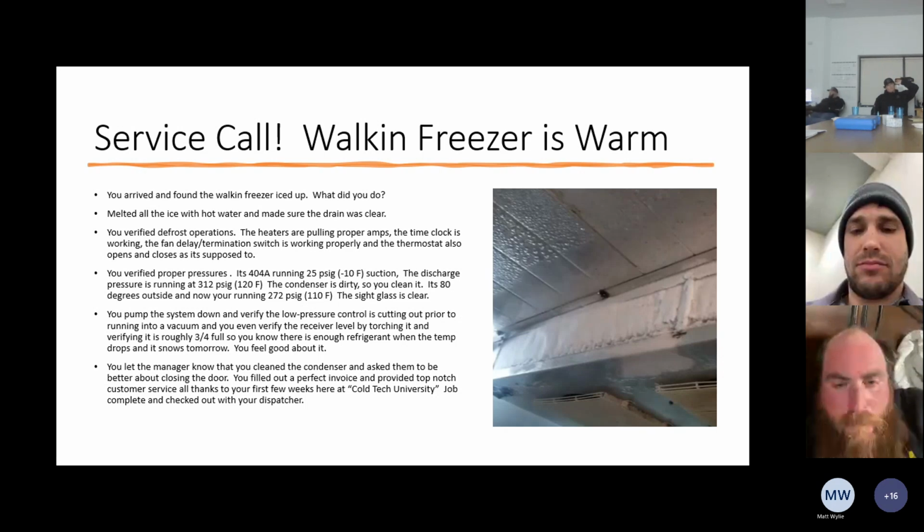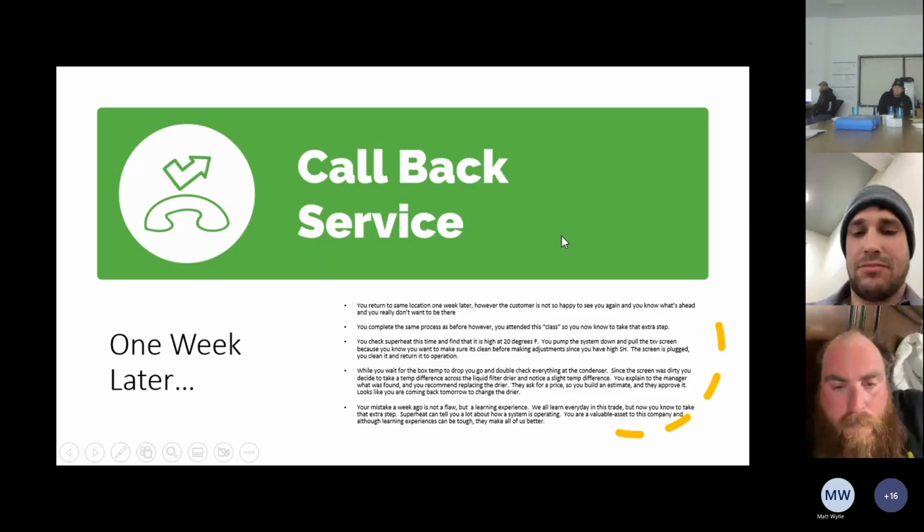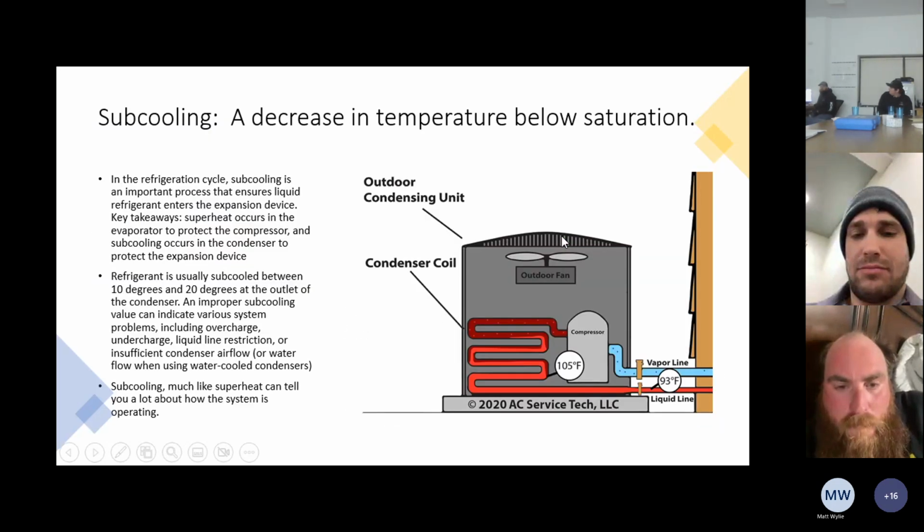It's just never crossed mine, Dustin. I believe it, Brad. I didn't even think about it. Yeah, it happens. You get in a routine of doing something and you miss it a few times, and before long, you're not checking it anymore until all of a sudden it's 10-degree, 15-degree plugged and not feeding refrigerant anymore. And you change out all the wrong stuff, and then you figure it out, then you check it every time.